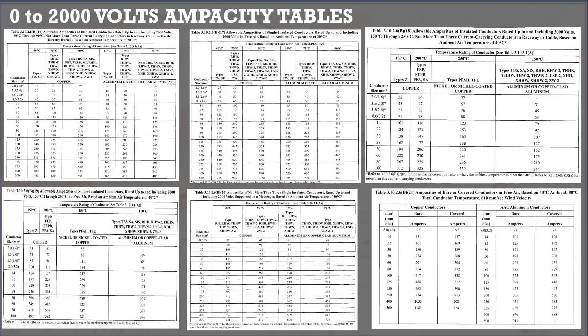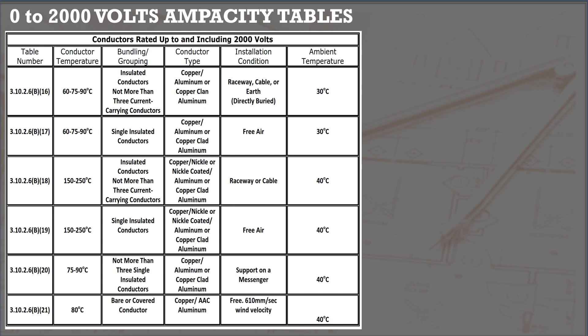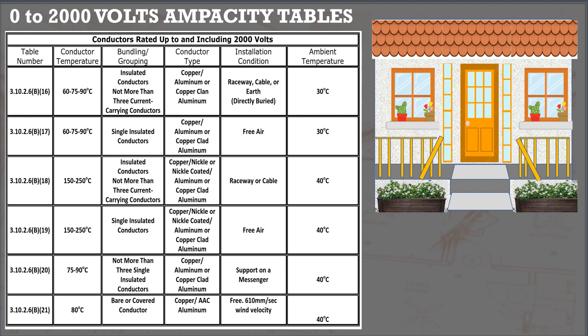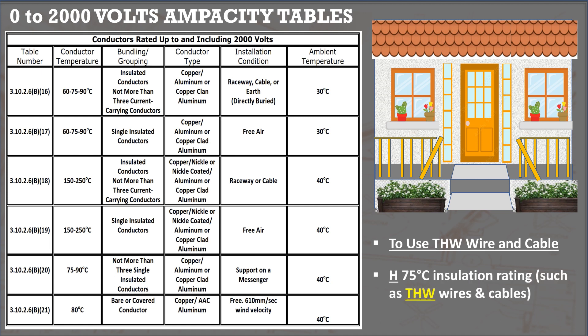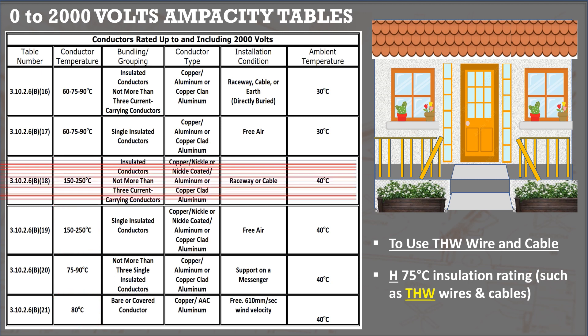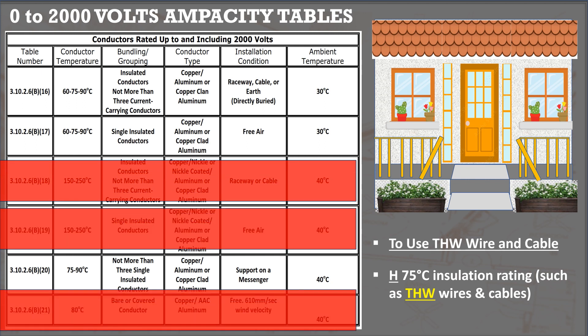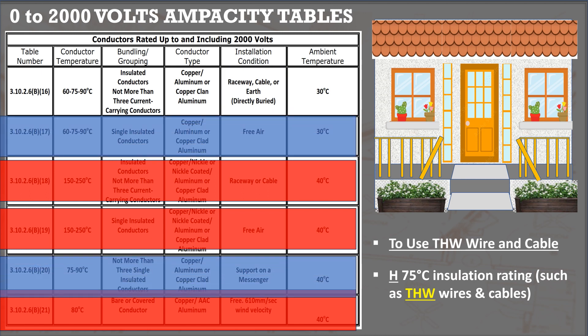How will we know which of the six tables to use for a particular project? Let's say we have a dwelling unit project using THW conductors with a temperature rating of 75 degrees Celsius. We can eliminate tables that do not have 75 degrees Celsius, leaving three tables. Since this is a dwelling unit installed via raceways, the other two tables are not applicable. Therefore, Table 3.10.2.6B16 will be used.